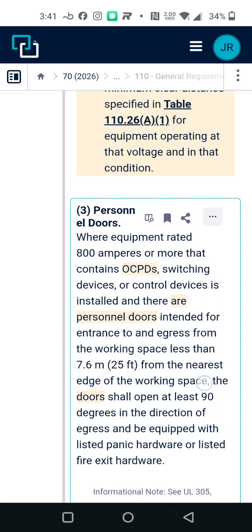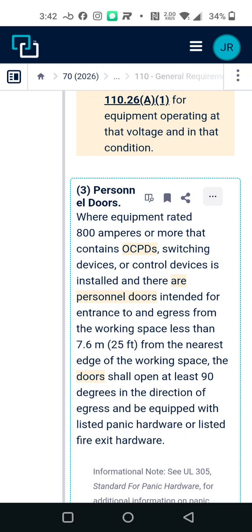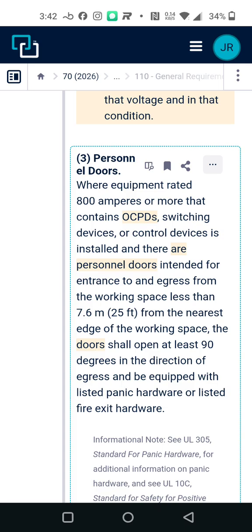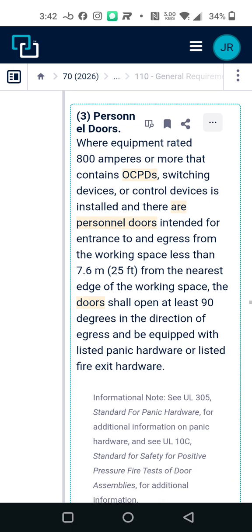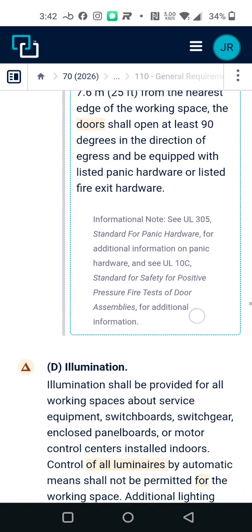Personnel doors, where equipment rated 800 amps or more contains OCPDs, switching devices, or control devices installed. There are personnel doors intended for entrance to and egress from the working space less than 7.6 meters from the nearest edge of the working space. The door should open at least 90 degrees.